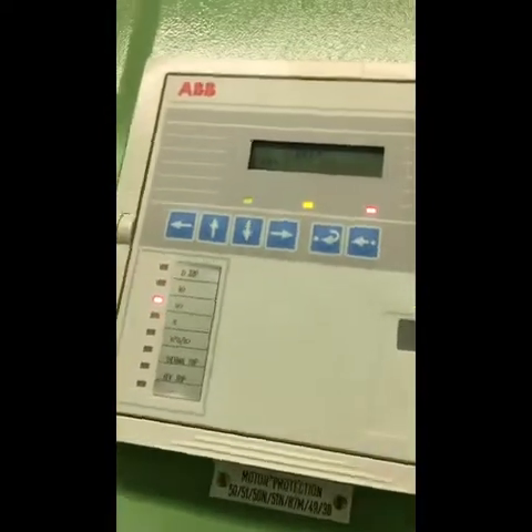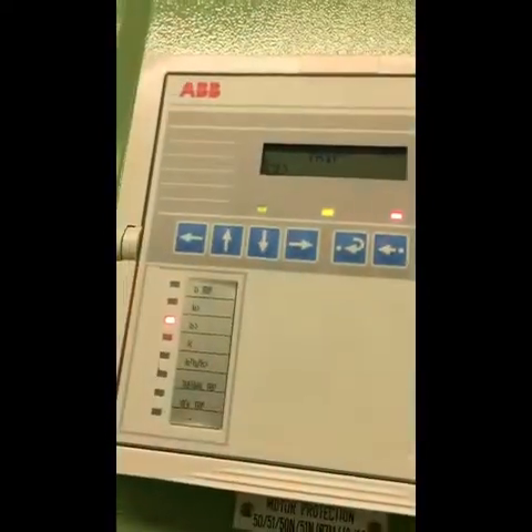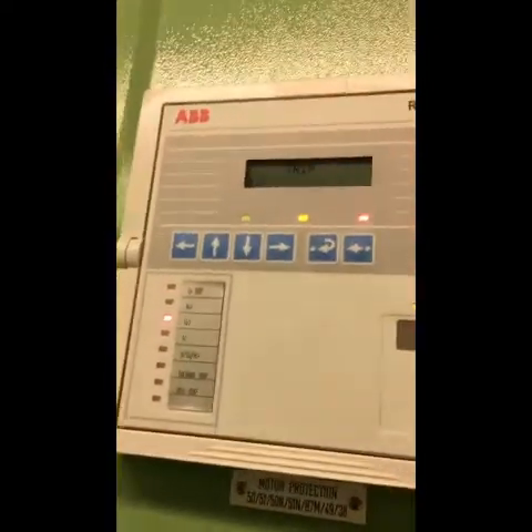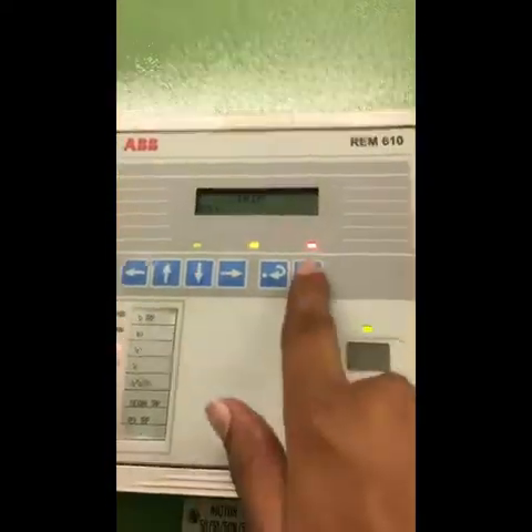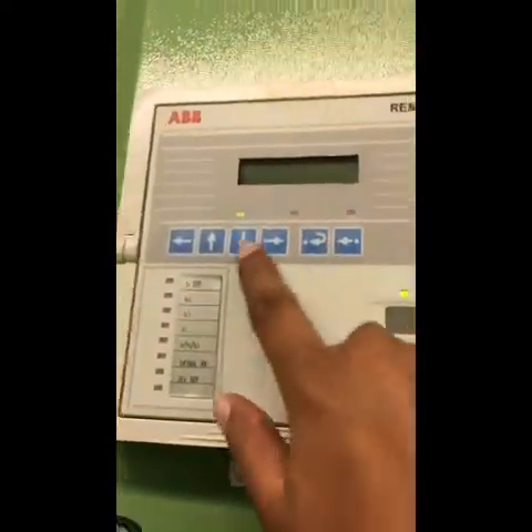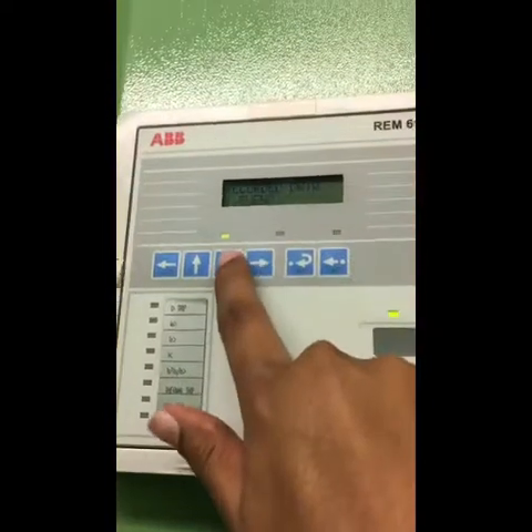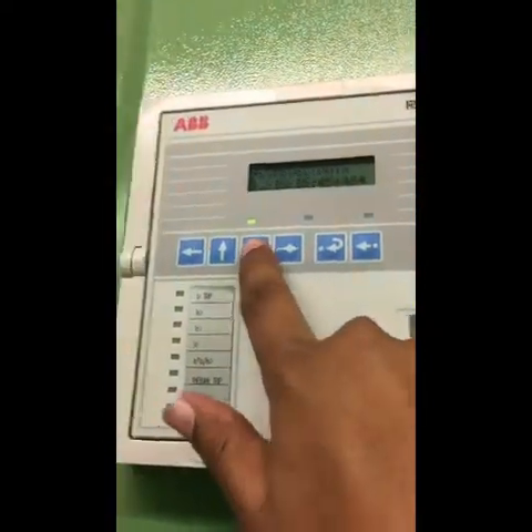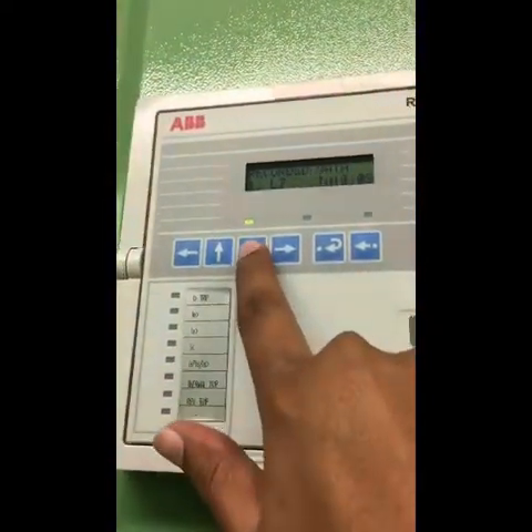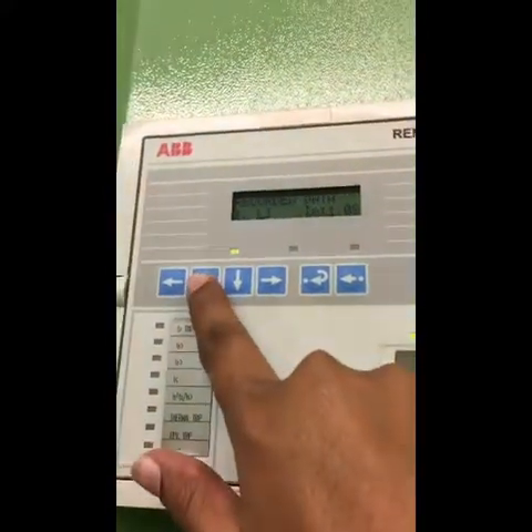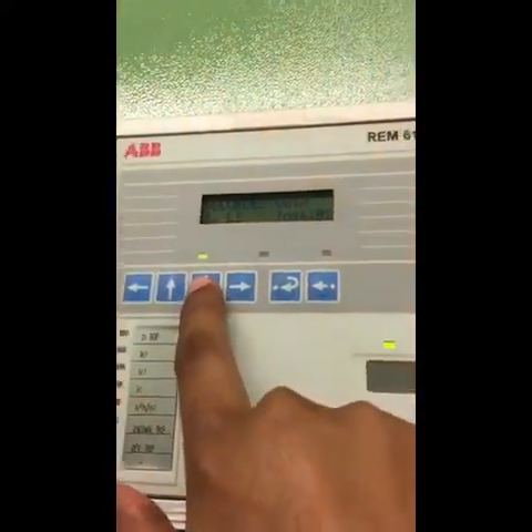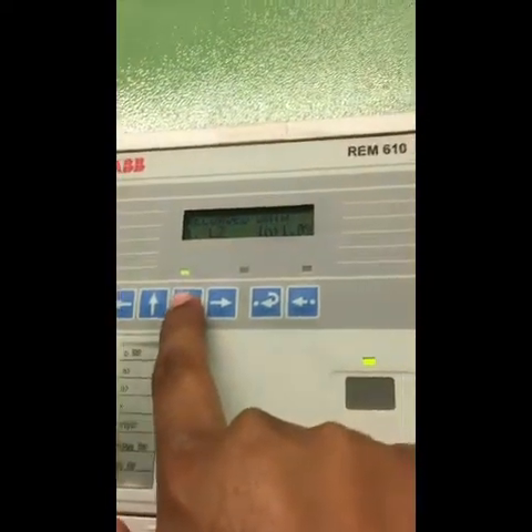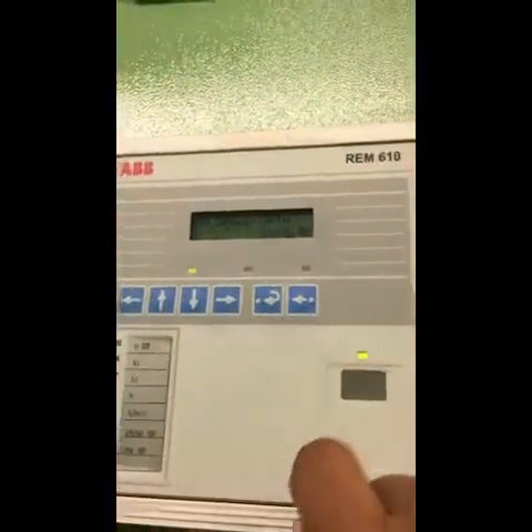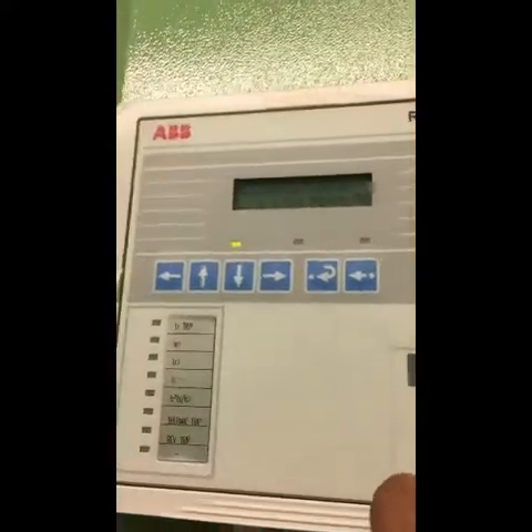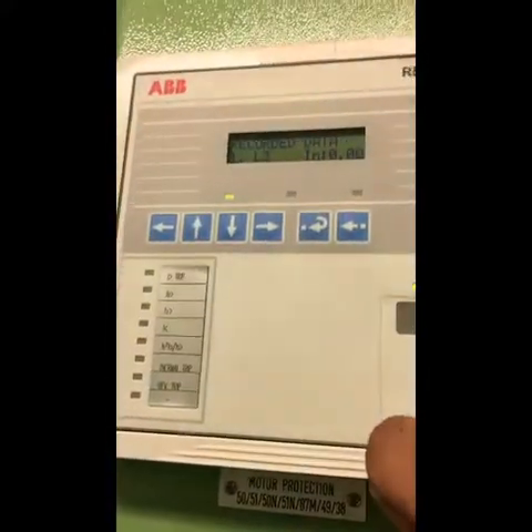A trip occurred, and it shows I2 greater, as I said, trip. We can see the reading, okay, we will reset. We will go to recorded data, event, the last event, the date, and as we see, line 1 there was current, line 2 there was current, line 3 broken, 0, means the line 3 current has been opened.